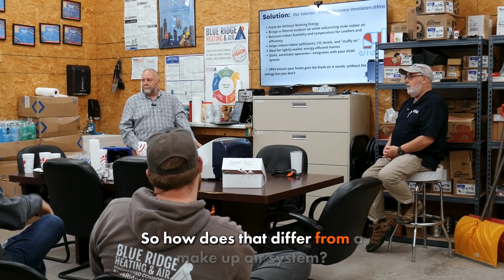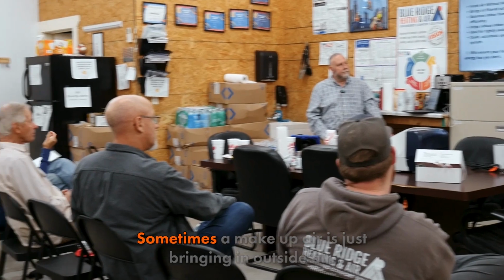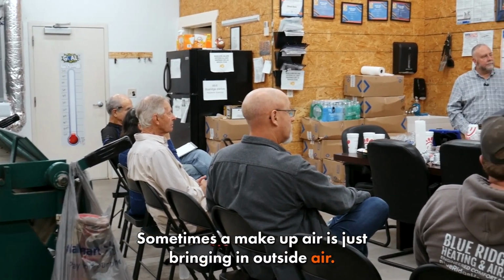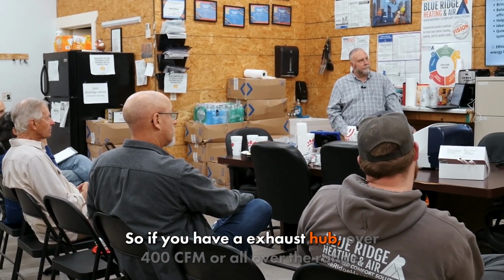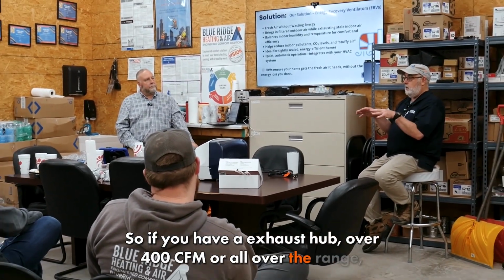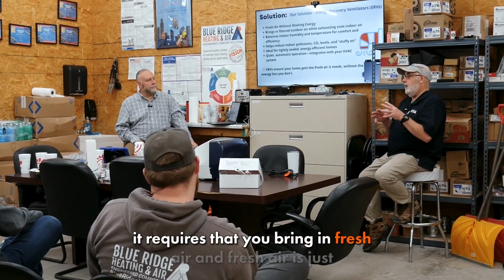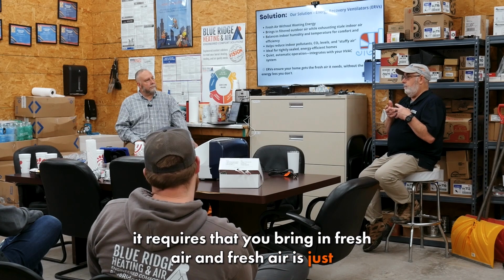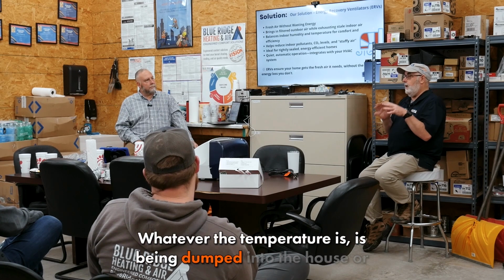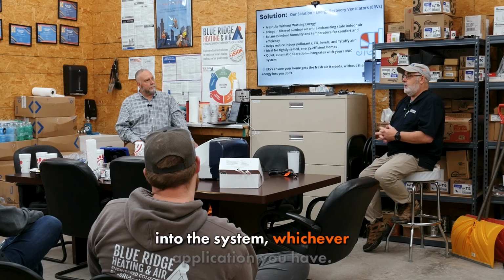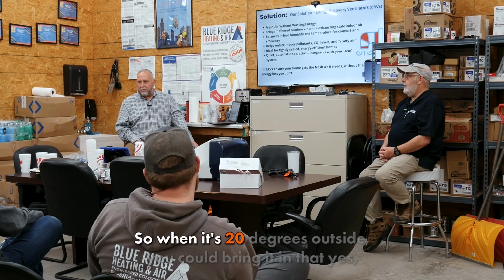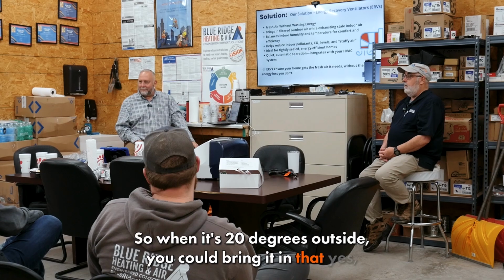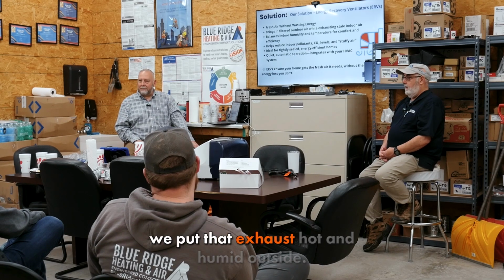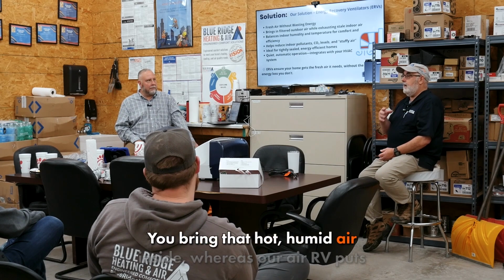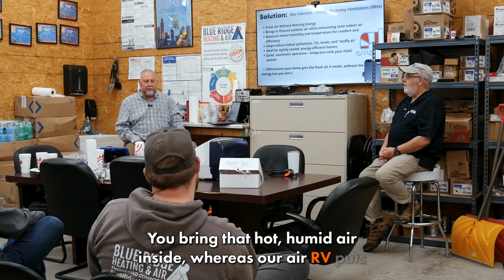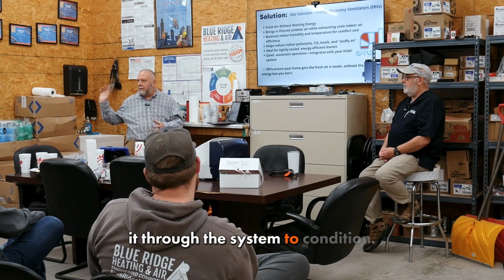So how does that differ from a makeup air system? Sometimes makeup air is just bringing in outside air. Say you have an exhaust hood over 400 CFM over the range, it requires you bring in fresh air. That fresh air comes in at whatever temperature it is and gets dumped into the house or the system. So when it's 20 degrees outside, you're bringing in that 20-degree air. Hot and humid outside, you bring that hot and humid air inside. Whereas our ERV puts it through the system to condition it first.